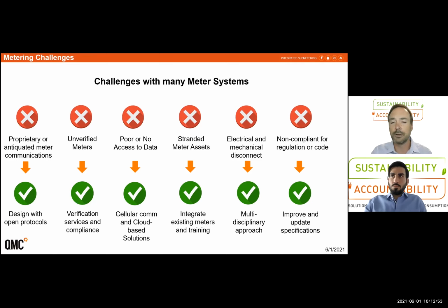And then lastly, systems not being regulatory compliant or up to code. So we've had water meters get installed that don't meet safe drinking standards, NSF 61, and need to get pulled out. We've had meters be put in place for billing that are not revenue grade. They need to get removed. So again, you need to ensure that any system you're putting in place is going to meet the regulations and codes of the region they're being deployed in.